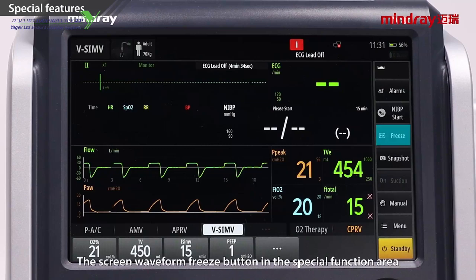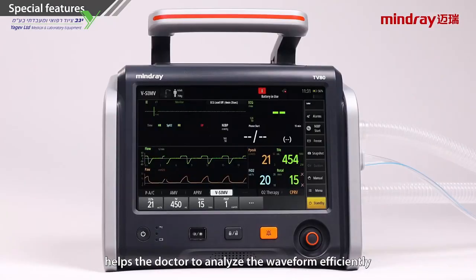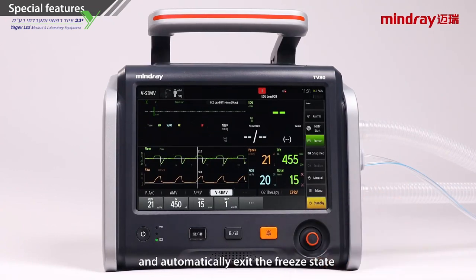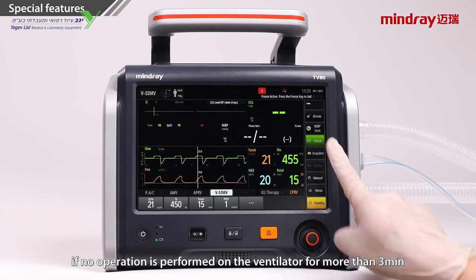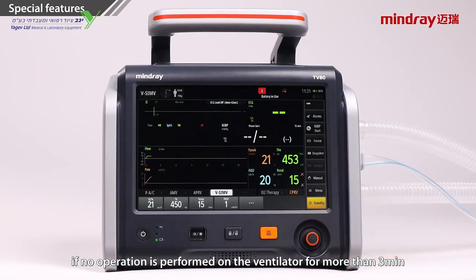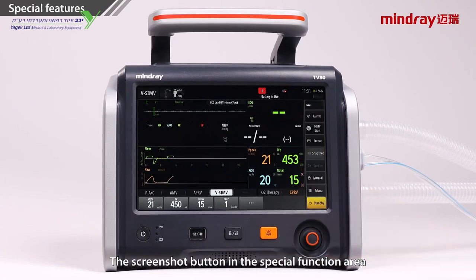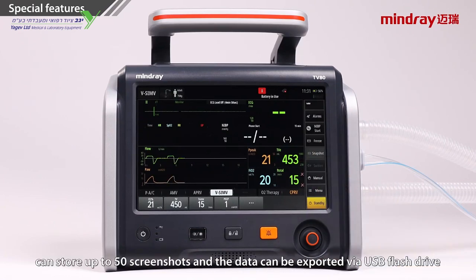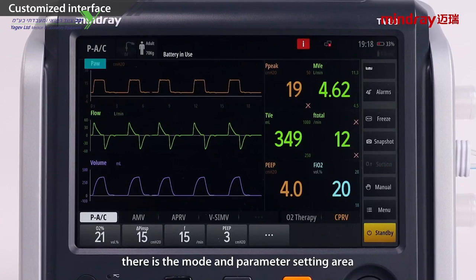The Screen Waveform Freeze button in the Special Function area helps the doctor to analyze the waveform efficiently, and it automatically exits the freeze state if no operation is performed on the ventilator for more than 3 minutes. The Screenshot button in the Special Function area can store up to 50 screenshots, and the data can be exported via USB flash drive. Further down there is the Mode and Parameter Setting area.